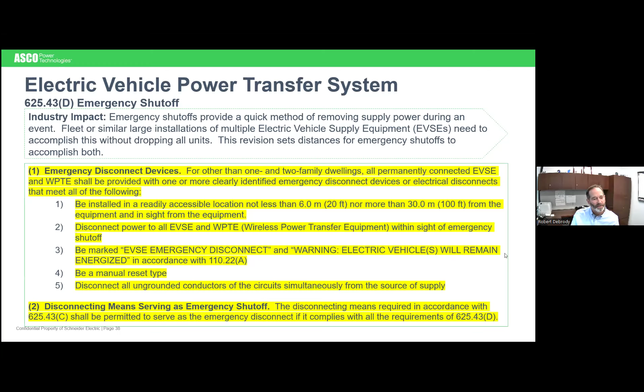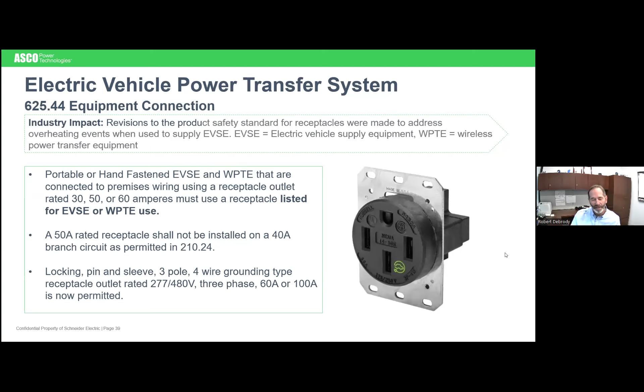And the last one I think I have here is just another paragraph that was modified. 3 sections. There's 3 things that they added. They want to make sure that you're using a listed type outlet. And that you don't have a 50 amp rated receptacle supplied by a 40 amp branch circuit, and their locking pin and sleeve are now allowed. And I guess it's probably easier if we just look at that complete paragraph. So here's how that paragraph looked in 2023 and how it looks in 2026 with those 3 things that I just mentioned outlined as changes.